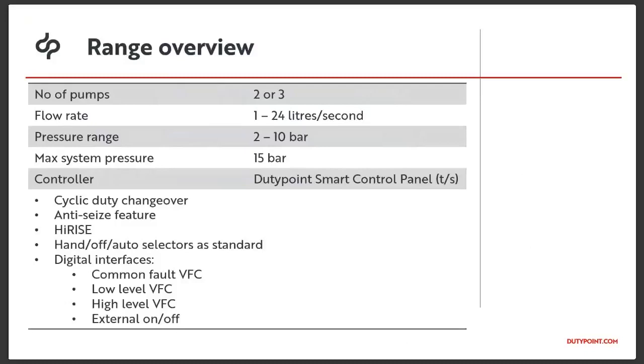It's got cyclic duty changeover to ensure even wear across all pumps. Then it's got a very good anti-seize feature, so in periods of low or zero usage, the pump set will spin up the pumps at very slow speed automatically to prevent them seizing up, so we can always be assured the pumps will be ready in good condition whenever you need them.